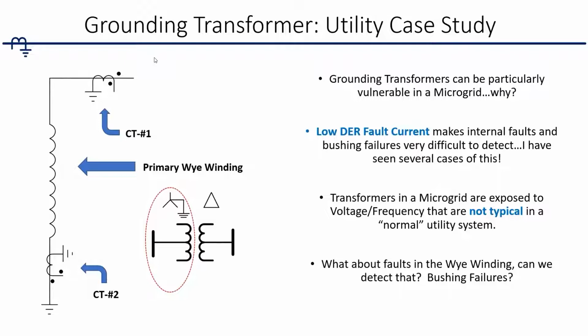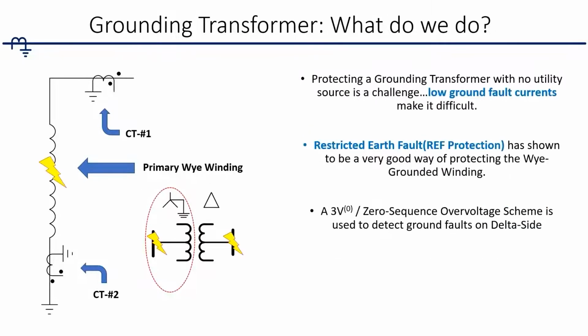So what do we do about faults down in this transformer? Inside the grounding transformer, how do we protect for that? A lot of utilities want to know that. What can we do to protect it? Protecting the grounding transformer, like we said, with no utility source is pretty challenging. There's not much ground fault current contribution from the inverter, so it makes it really difficult.